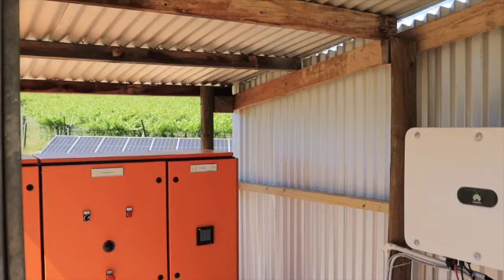The pump is currently running in grid-tied mode, and now load shedding kicks in. The grid-tied system switches off as per regulation, and the solar pump VSD starts up slowly — taking a few seconds to start putting in the solar, starting the pump, and running it completely off-grid. This is an ideal scenario for load shedding risk mitigation. Now we're simulating the grid coming back in — and there it is, the system has moved over from solar pump mode back to grid-tied mode. That's typically how the system will run.